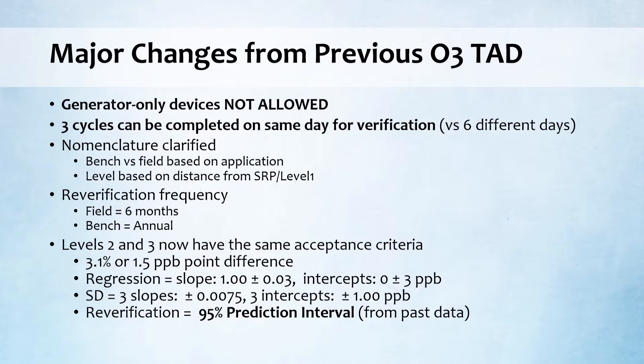The nomenclature has been clarified. Bench versus field is based on application — bench is a standard that is stationary, field is one that's moved from station to station. The level is based on the distance from the SRP. Our transfer standard is currently considered a level three because it's used in the field, but going forward it's going to be considered a level two because it's verified directly against the level one and used in the field — so it will now be considered a level two field. The re-verification frequency will still be the same six months for field transfer standards, and a bench standard requires re-verification annually.